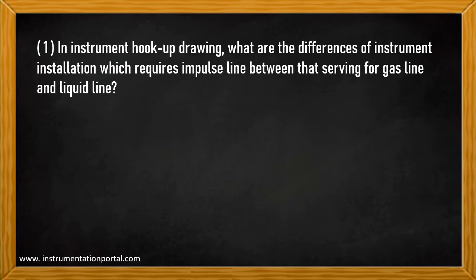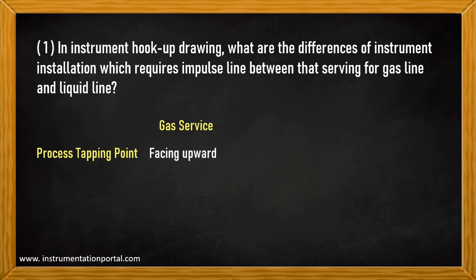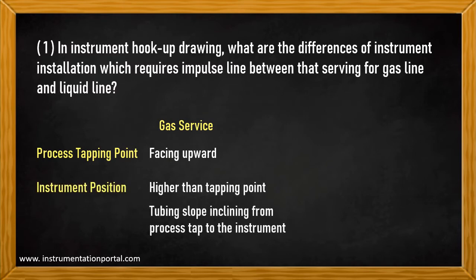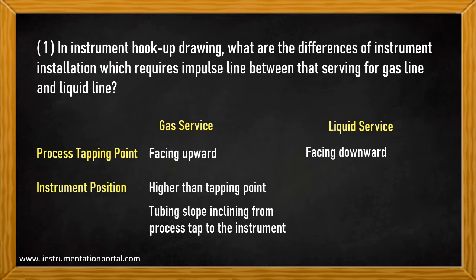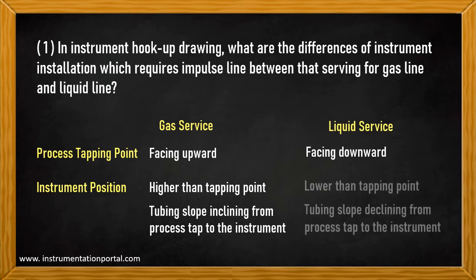Question number one: in an instrument hookup diagram, what are the differences in instrument installation requiring impulse lines between gas service and liquid service? In gas service, the process tap shall face upward, the instrument is mounted higher than the process tap, and tubing shall slope inclining from the process tap to the instrument to allow self-drain of any liquid component back to the main piping. In liquid service, the process tap shall face downward, the instrument is mounted lower than the process tap, and tubing shall slope declining from the process tap to the instrument so that any gas component in the liquid can go back to the main piping.